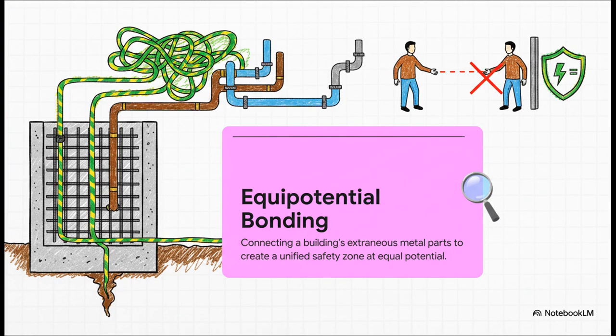The next level of protection has a fancy name, equipotential bonding, but the idea is pretty simple. It's about connecting all the other metal things in a building, like water pipes, gas lines, the steel frame itself, and hooking them all up to the main earthing system. This makes sure that if there's a fault, everything is at the same electrical level, which gets rid of dangerous voltage differences between things you might touch at the same time.